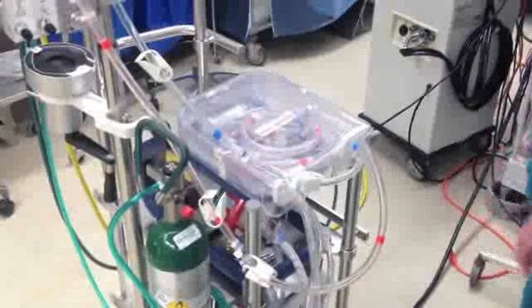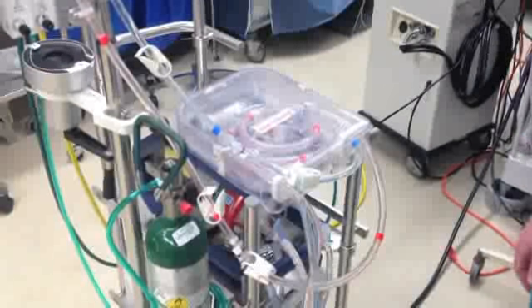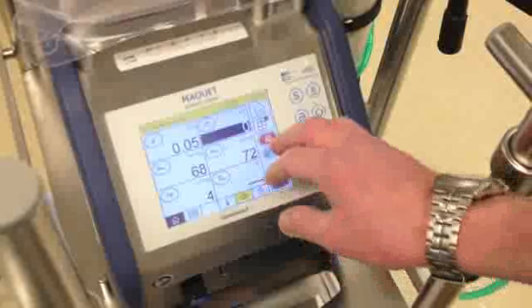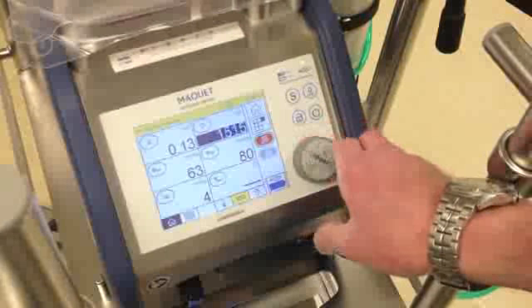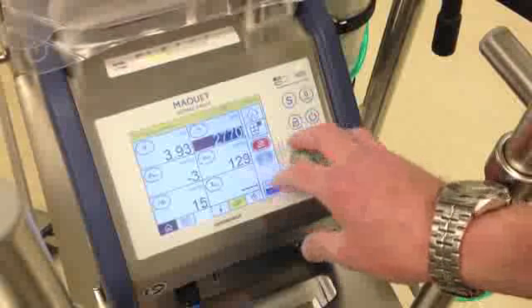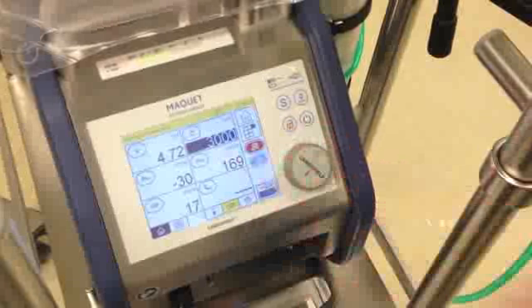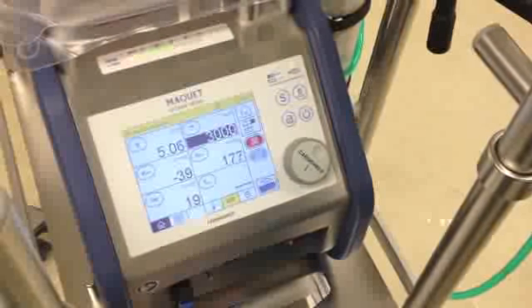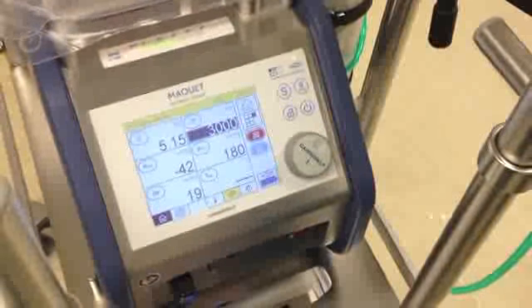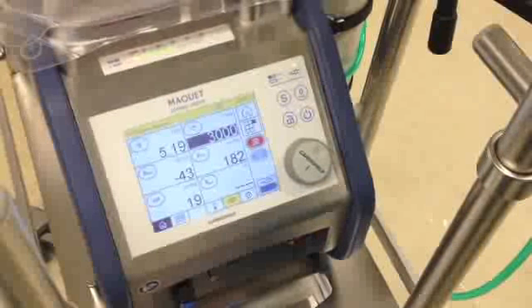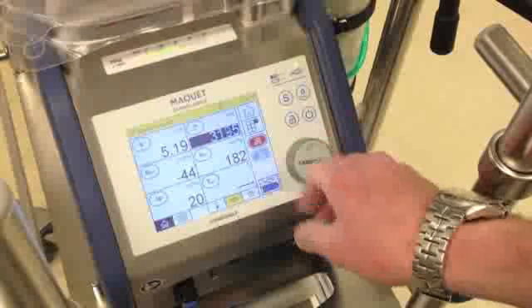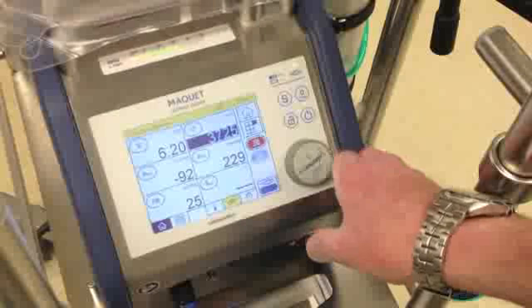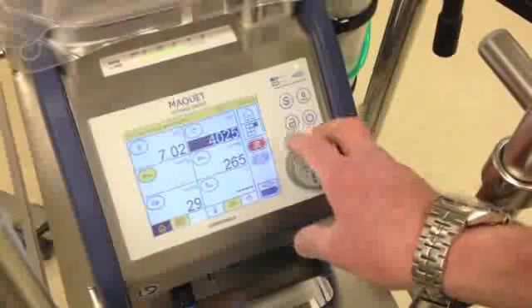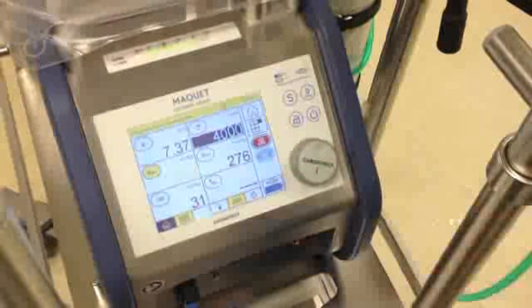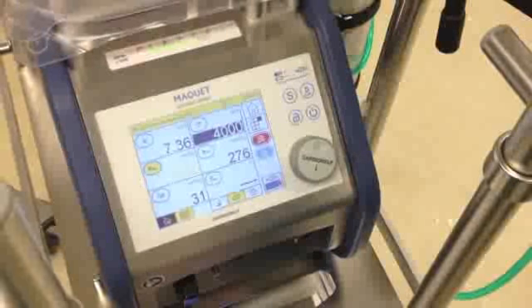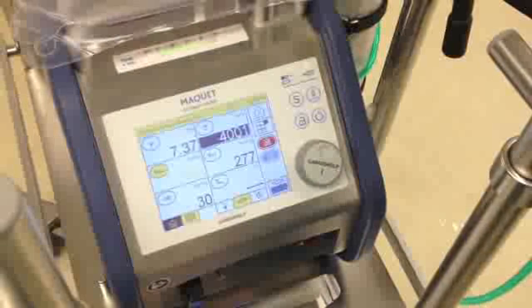Now he will unclamp the blue line, and flow will start going from the prime line into the CardioHelp console. At this point, you'll increase your RPMs to 3,000. You'll let it run there for 2 minutes, and then you'll go to 4,000 for a minute. And this is done to flush the air out of the system. If you still hear air in the system, you'll repeat those steps. Go to 3,000 for 2 minutes, and then back up to 4,000 for a minute. But it shouldn't have to be repeated.